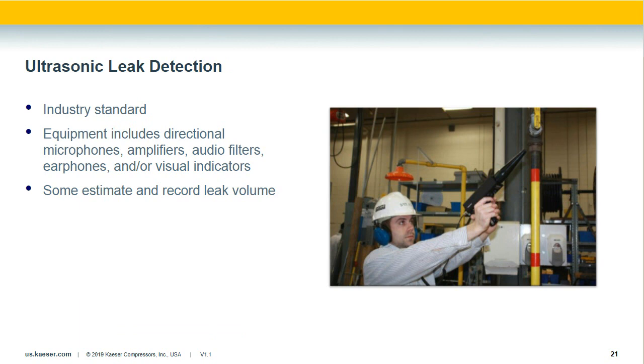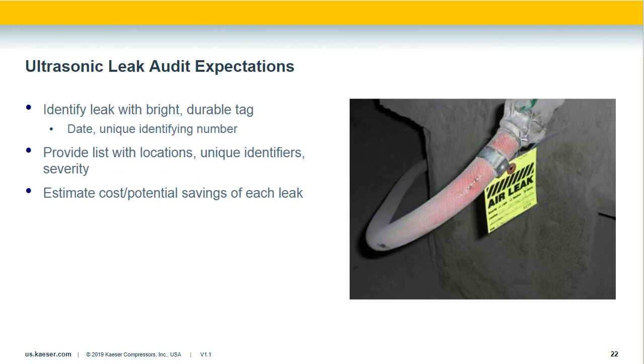The industry standard for leak detection is ultrasonic. Ultrasonic leak detectors require specialized equipment and some training. They provide a volume level for each leak — an estimate of the volume and the cost — helping you prioritize which leaks to fix first. If you can hear a leak without a detector, fix it immediately; it's costing you a lot of money. When you have a leak audit done, make sure each leak is tagged and clearly identified, you receive a complete report, and the audit provides estimated cost and savings potential with pictures of each location.